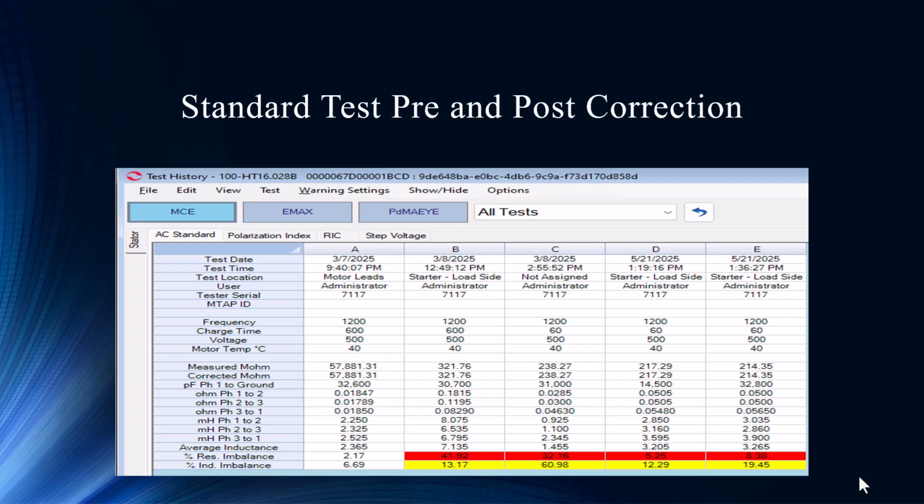It'd be worth taking current ammeters, take your Emax test, get on those two cables and see if there's a different flow from one cable to the other. You may find a situation where the large majority of current is flowing through one of the two parallels, in which case it's going to significantly increase the resistance of that conductor. And that could relate it to a 5% resistive imbalance. Okay, those are all good ideas that you can add into this.